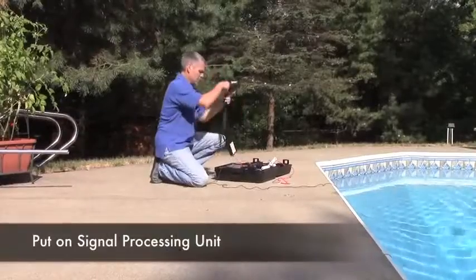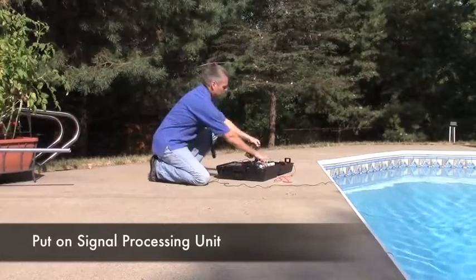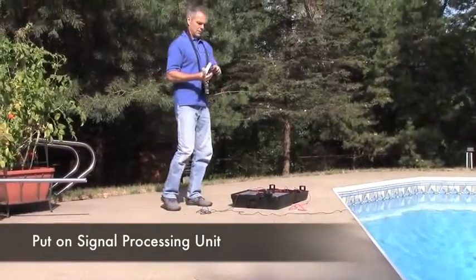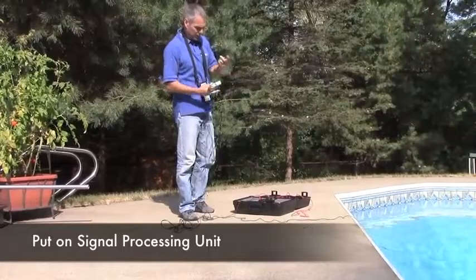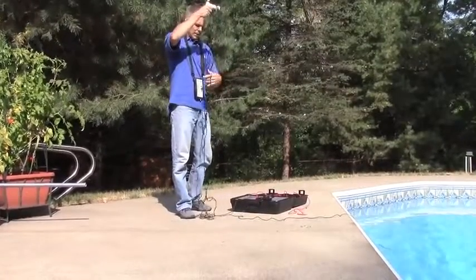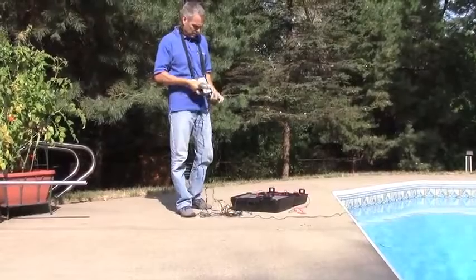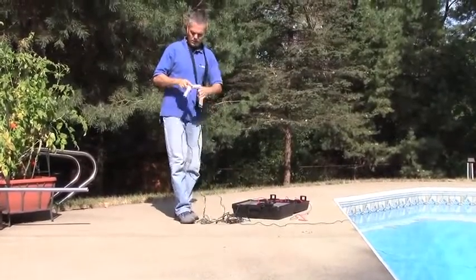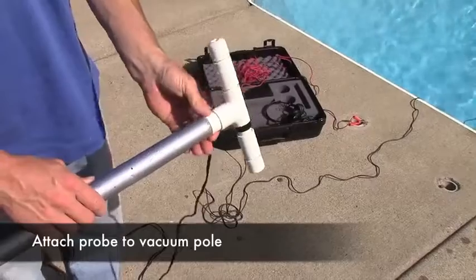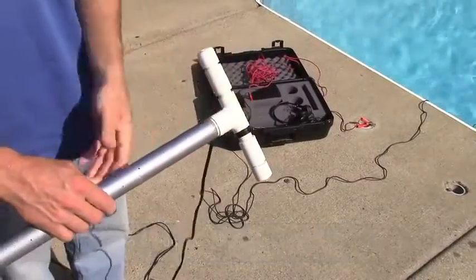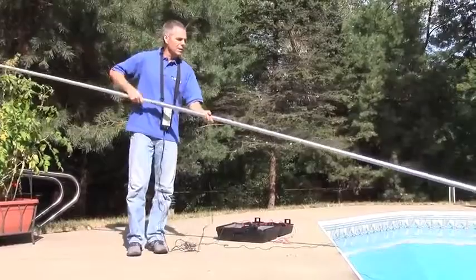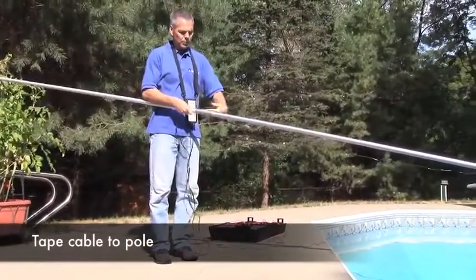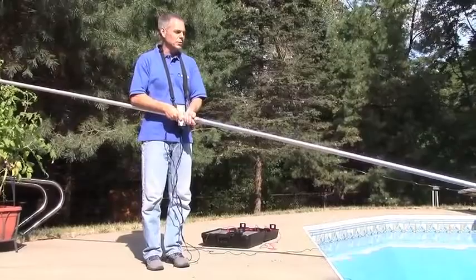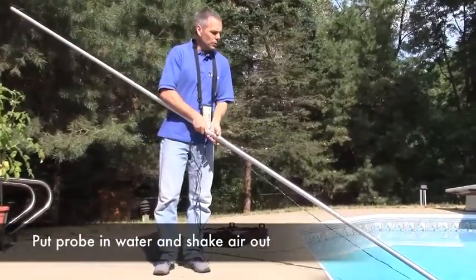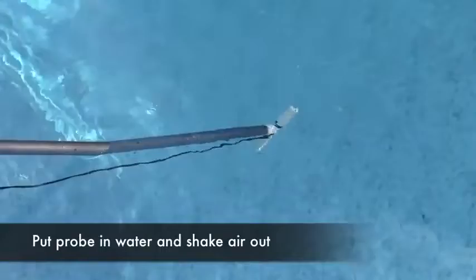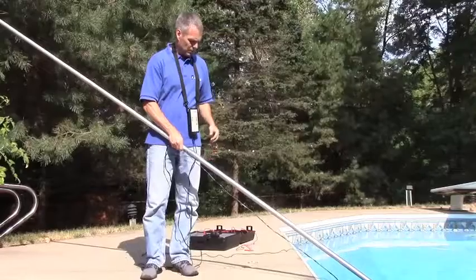Finally, the signal processing unit gets put around our neck, and our probe gets plugged into the back of that signal processing unit. The probe then gets attached to a vacuum pole. I like to pull the cable up the length of the pole, and I'm often going to tape the cable to the pole so it's out of our way as we use it. Finally, the probe goes in the water, and we're going to shake the bubbles out, turn the unit on, we're ready to go.